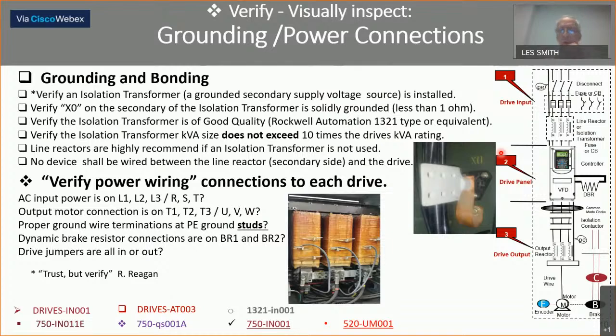Grounding and power connections. That's one of the first things I go to. Now you notice here, our reference here is still the quick start at the top for that question, but you see the solid triangle, that's in the AT003. On the quiz, a lot of those questions are related to that, but they phrased them so they were easy to use here. Verify that an isolation transformer is installed or not, but be aware of it. Is it grounded or not? Verify that X0 on the secondary of the isolation transformer is solidly grounded. Less than 1 ohm is the definition of solid ground.